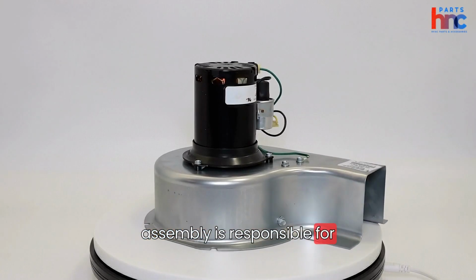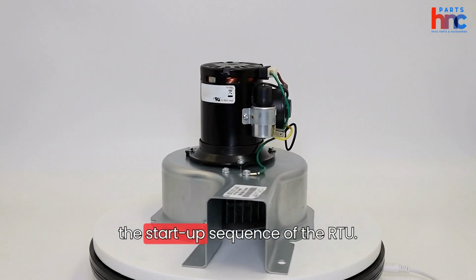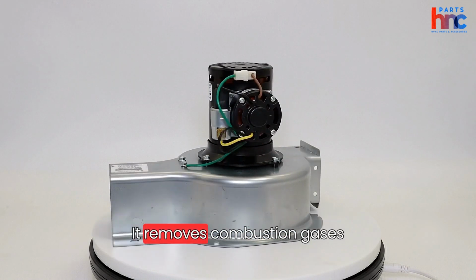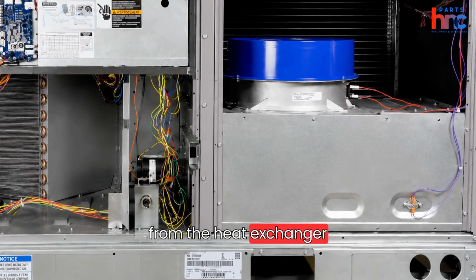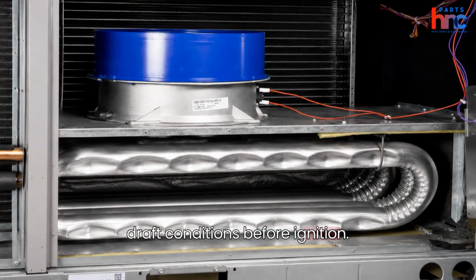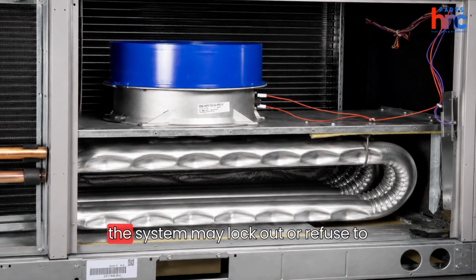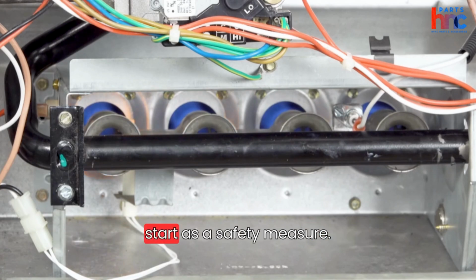Welcome to PartsHnC. The inducer assembly is responsible for creating proper airflow during the startup sequence of the RTU. It removes combustion gases from the heat exchanger and ensures safe draft conditions before ignition. If this component fails, the system may lock out or refuse to start as a safety measure.